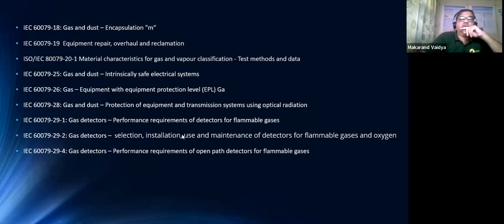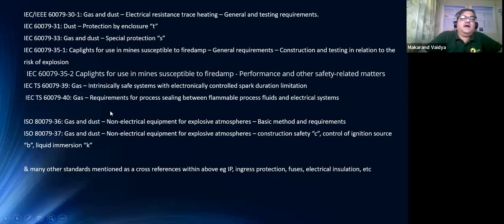So these are all equipment, performance, etc. And here comes another category not covered in IEC, which is electrotechnical. So non-electrical equipment in hazardous areas is covered by ISO, not IEC. During my journey in this field, I also had to deal with other standards like ingress protection, fuses, electrical insulations, materials of construction, and so on. These things you have to take care of while working in this business.